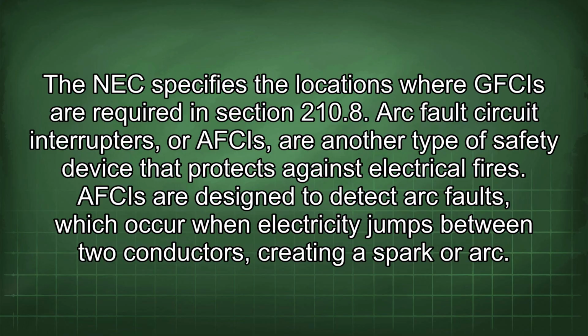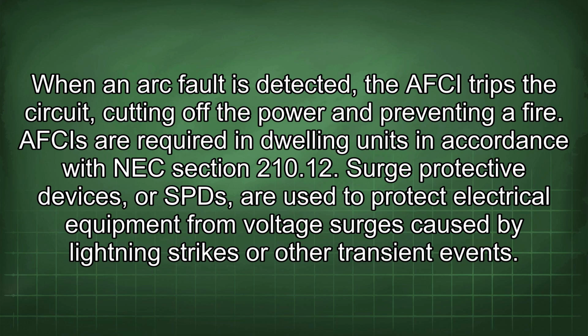Arc fault circuit interrupters, or AFCIs, are another type of safety device that protects against electrical fires. AFCIs are designed to detect arc faults, which occur when electricity jumps between two conductors, creating a spark or arc. When an arc fault is detected, the AFCI trips the circuit, cutting off the power and preventing a fire. AFCIs are required in dwelling units in accordance with NEC Section 210.12.